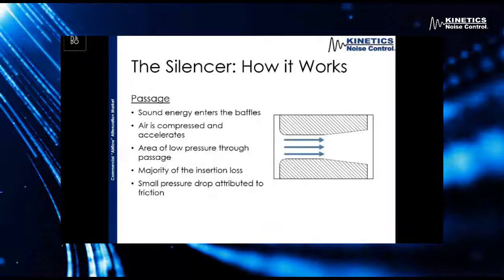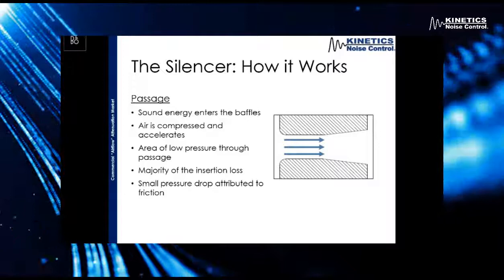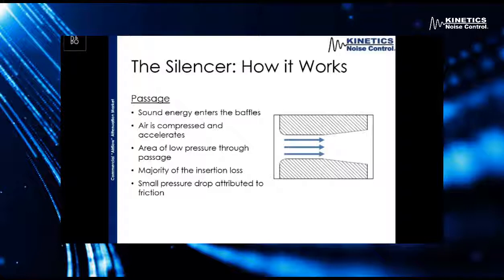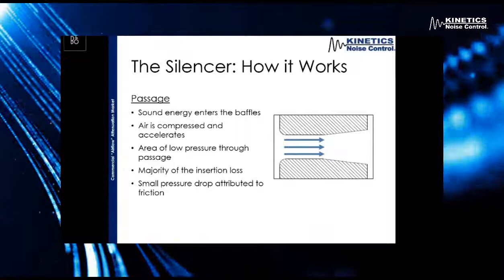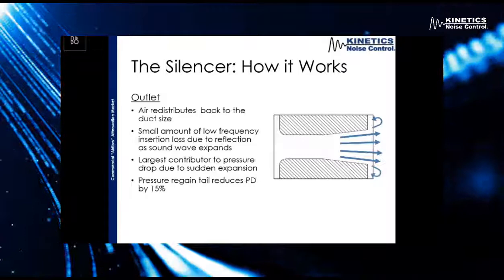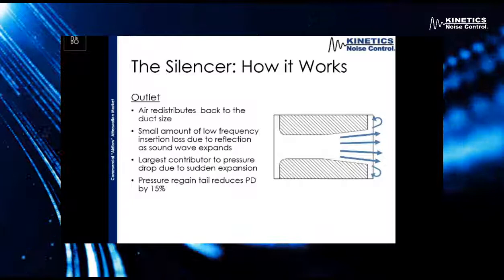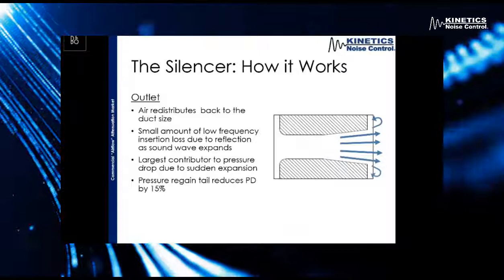Next, through the passage of the silencer, this is where the majority of the insertion loss happens. The airflow comes in between the baffles — it's compressed and accelerates — and that sound energy goes through the perforated sheet metal to the acoustic media where it's dissipated. We do get a small amount of pressure drop here as well, but definitely not a significant amount — it's mostly just due to some friction losses as that air travels over the perf. Then lastly, we have the outlet of the silencer, where the air is redistributing back to the duct size. We get a small amount of low-frequency insertion loss here — there's a little bit of reflection of the sound wave as that air expands. But this is also going to be the largest contributor of pressure drop, due to the sudden expansion of that air back into the ductwork size.